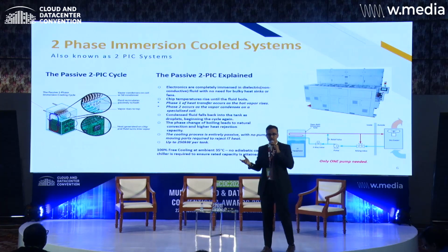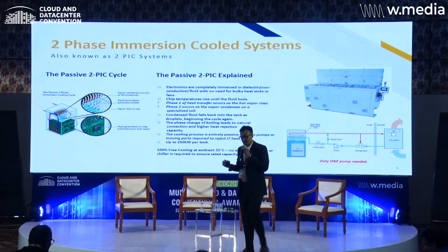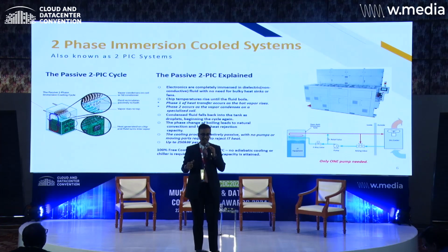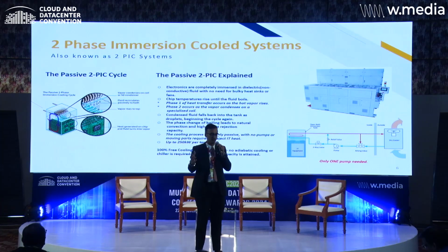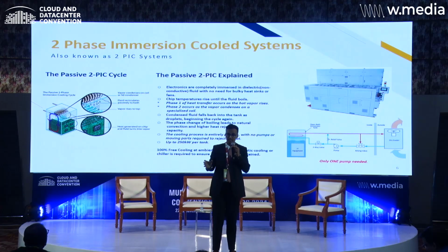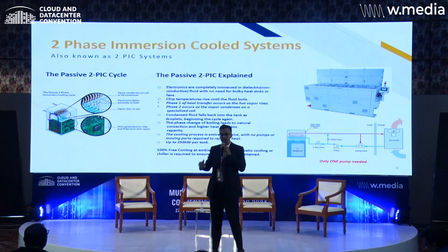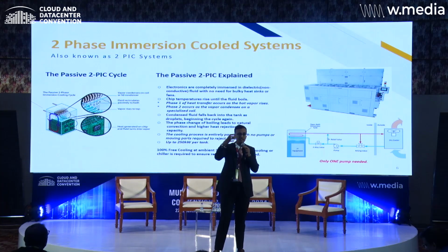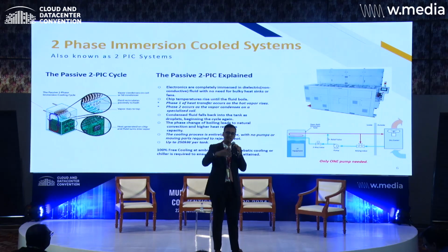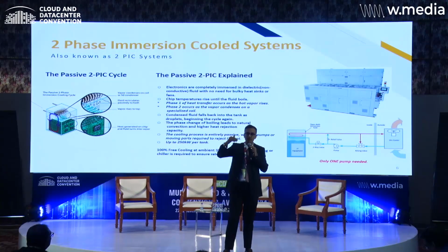This is what two-phase immersion cooling does. It's a great technology and so simple. What it does is, we have a dielectric liquid which is completely fire-free and does not conduct electricity. When the chip heats up to 50 degrees, the liquid boils, and as any liquid would when it boils, it turns into vapor.